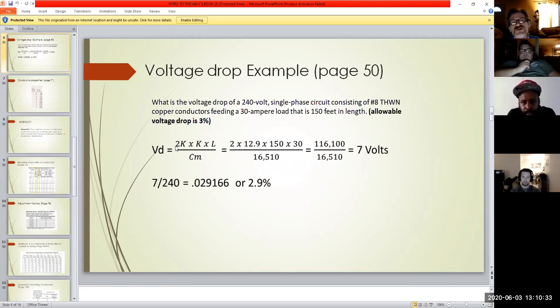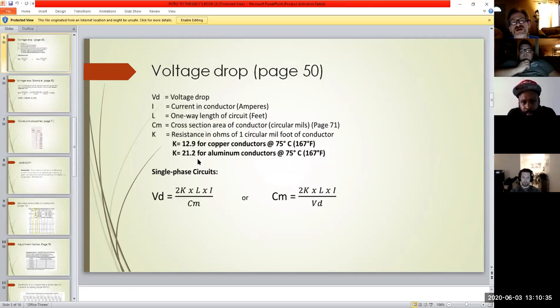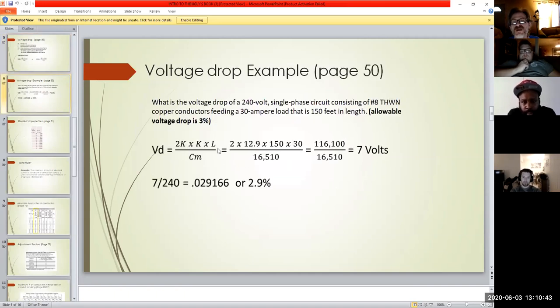But it's really not that bad. The K part, as you see right here, that's just for what kind you're using, whether copper or aluminum. That number doesn't change. And the current, you're going to have the current, right? You'll be like, okay, I got a 30 amp breaker in there, so that's what the current would be.